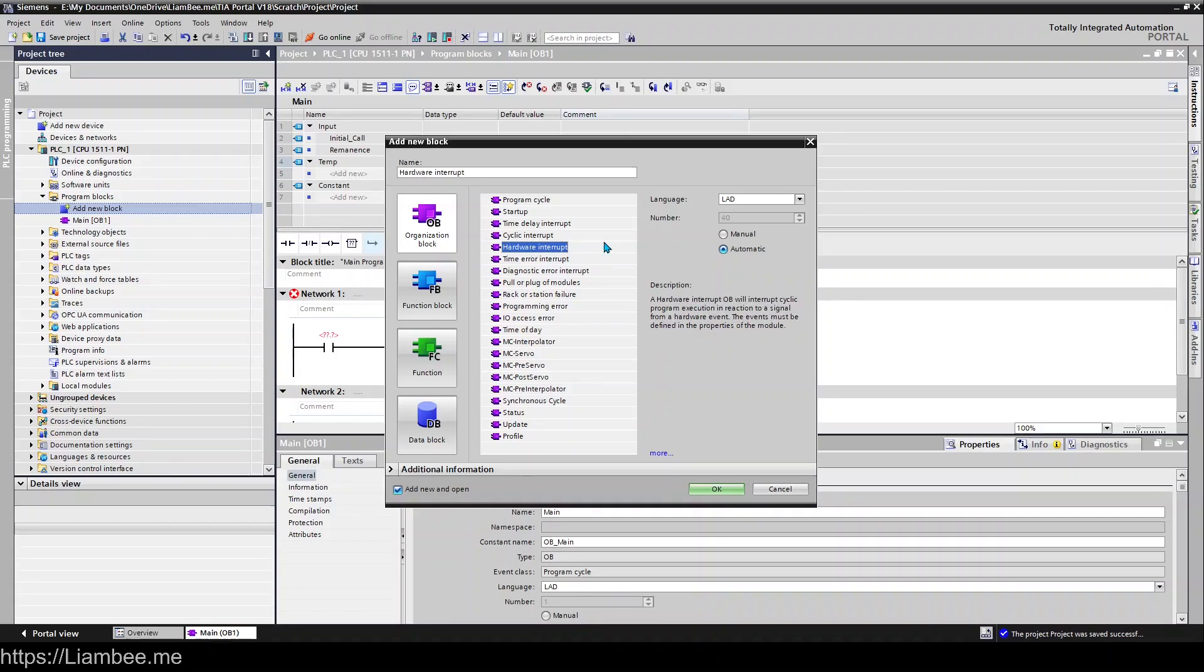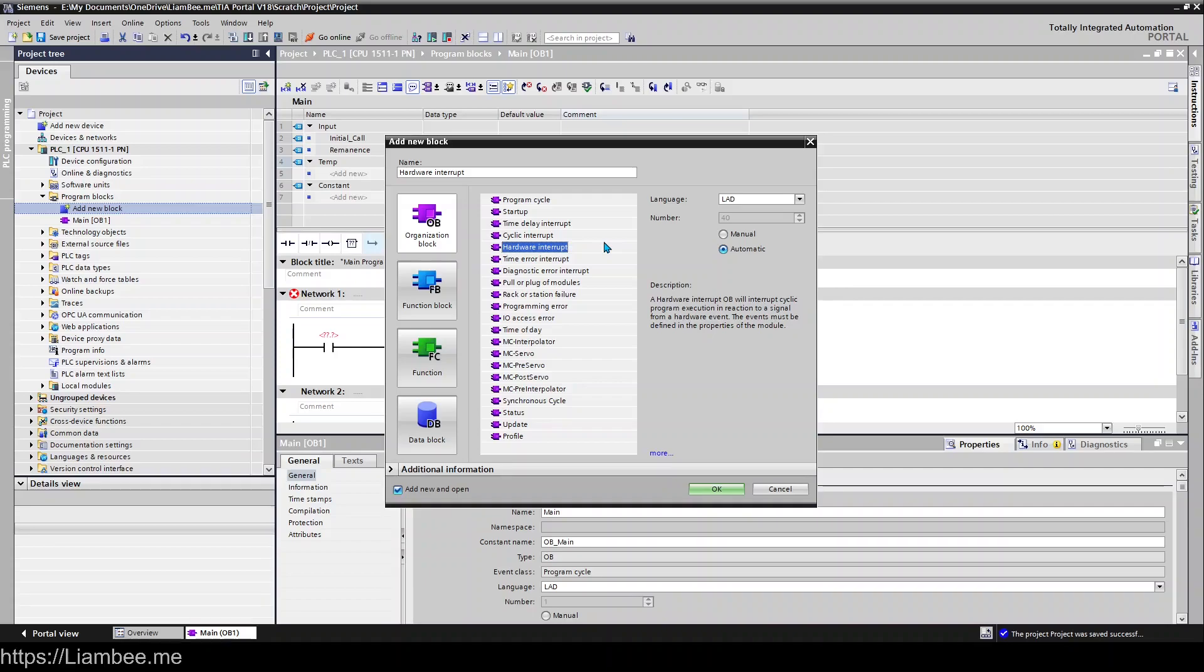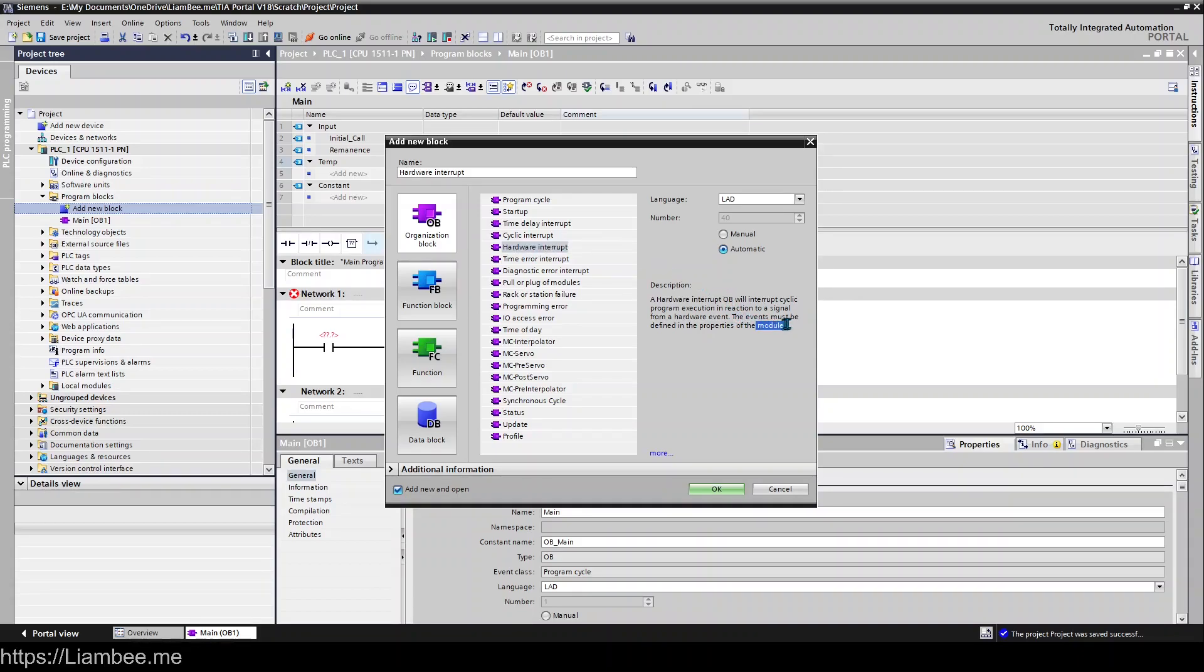Hardware Interrupts, which interrupts the program cycle if particular things happen to your hardware, such as an event where somebody unplugged a module or something went into fault. There's lots of different things that can cause hardware interrupts. You need to refer to the documentation and the event must be defined in the properties of the module. So you need to actually configure it to cause a hardware interrupt.